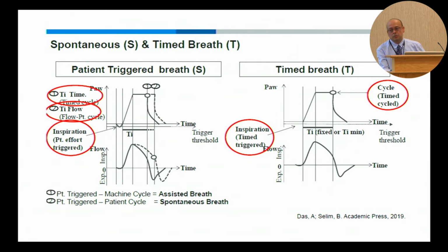So when you put AVAPS on Respironics under ST, Respironics is going to treat your own breath as a flow trigger. And the machine breath is going to be triggered by time. So it can be confusing when you are doing the titration if you have a Respironics device, because if you put it on ST, you're only going to get the I time attached to the breaths that are triggered by the machine. And when the patient is triggering, that's triggered by flow. And that's different because flow is effort dependent. So it's variable, whereas time is based on time.